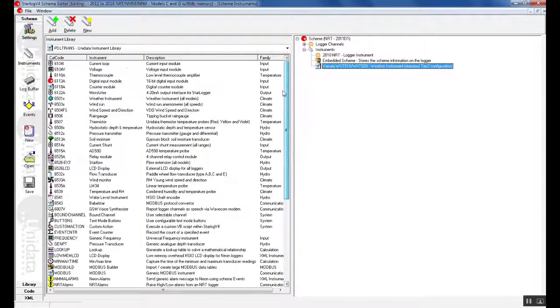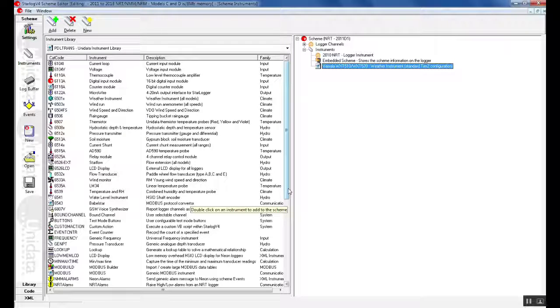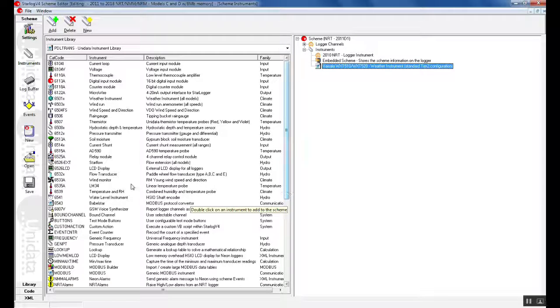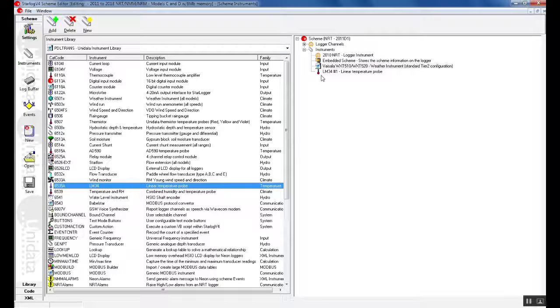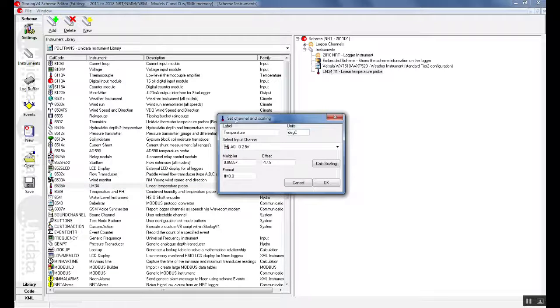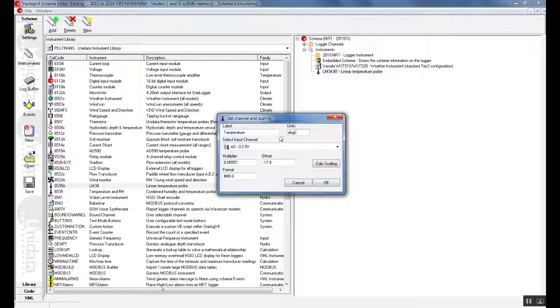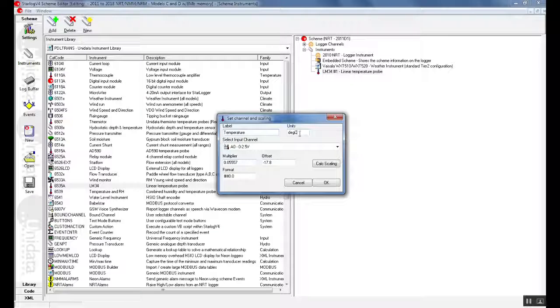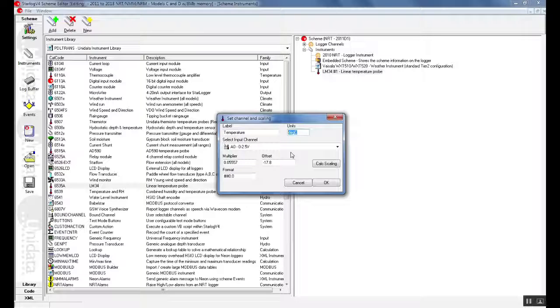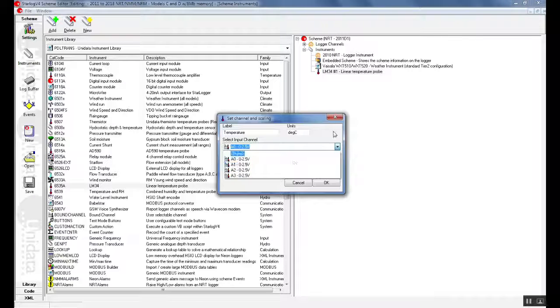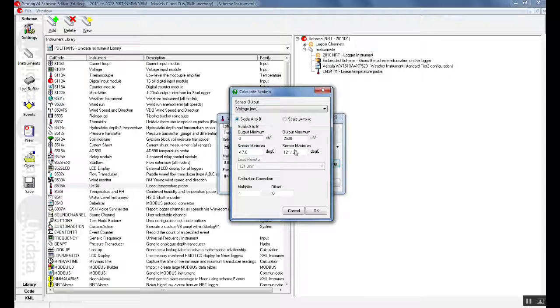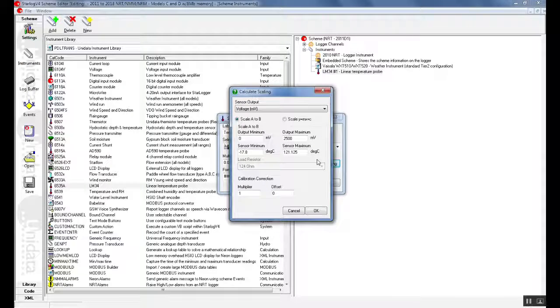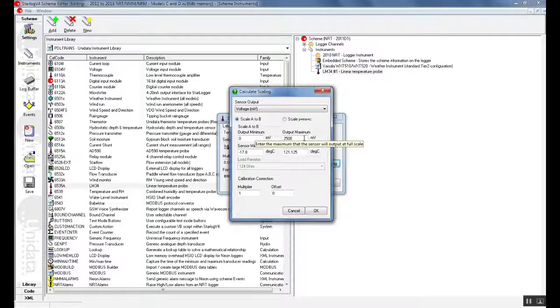Another instrument we can add is a temperature sensor. The Unidata temperature sensor is known as a LM34 or a 6535A. Here we will select it here. As you can see now this has been added to the right hand of the screen. This has been automatically set up as well. Once this is set up we can either change the name to something else we would like. We can also set the units to something else we want and the analog channel that we are connecting the temperature sensor to. If we also click on calc scaling we can modify our output. Now if we were using our own temperature sensor and it had a different range we could change the range here.